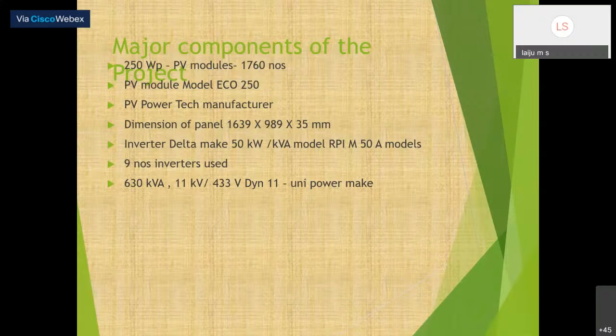433 volt. So 433 volt three-phase should be converted into 11 kV depending on the power evacuation requirement. So as per regulation, we can say that up to 100 kilowatt, we can connect it on the LT side, but above that, it will be on the HT side. That is, power evacuation is required at 11 kV. So the next step is we have to step up the 433 V into 11 kV. We are using a 630 kVA transformer, 433 V by 11 kV, to step up the power for evacuation.